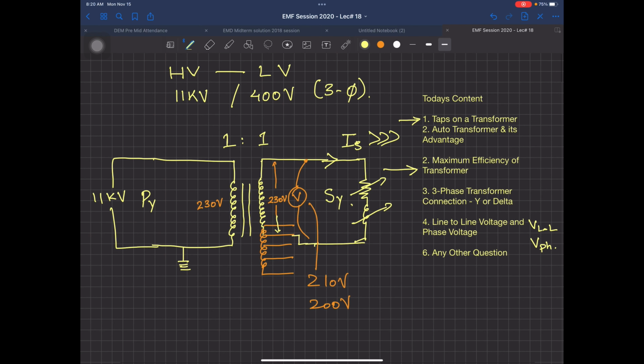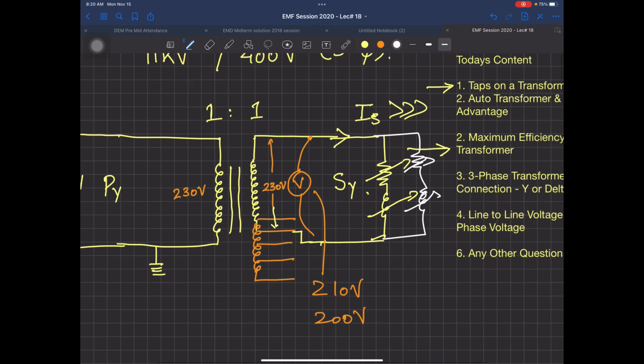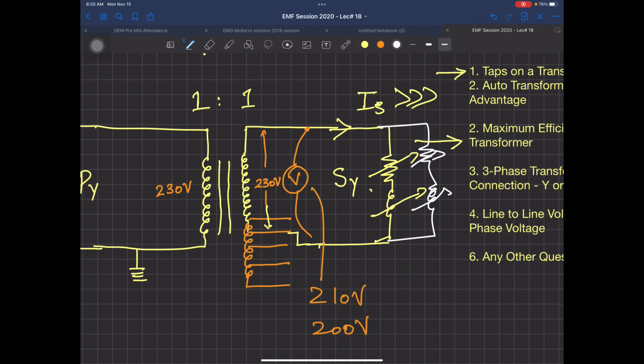Now on this side you will have a lot of other homes also connected in parallel, because all the homes in your street are connected in parallel. The problem here is that if the load increases, the voltage is not sustaining 230 volt. So you have to change the tap. Practically this can only be changed by climbing on the transformer pole and changing the connections physically.